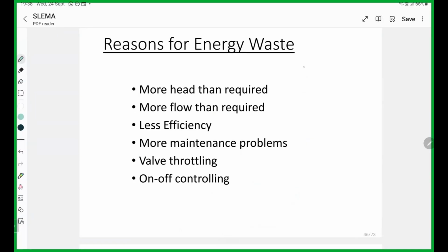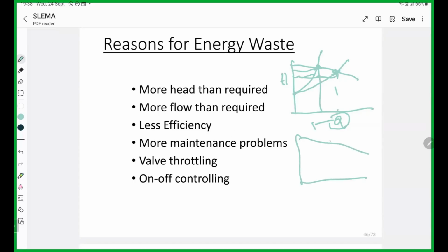Say this is the pump curve, right? This is our selection point, this is Q, and this is head. Our selection is this one, but our required Q is less. What do we do? We control the valve, and we are losing energy. If your valve throttling is losing energy, and the head is higher than what is required, then our design point is somewhere here, but the actual head is somewhere here. Then definitely the pump energy consumption is high, and the efficiency drops.